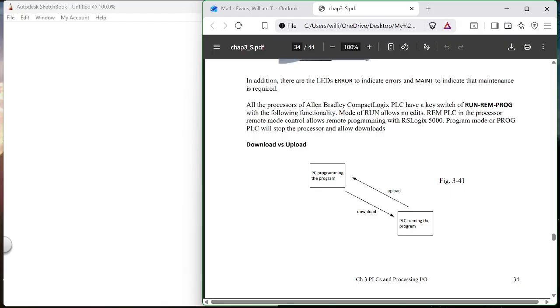And then there's a little green square in the Allen Bradley upper left. It's turquoise or green, and also both of them have what I call goalposts. Allen Bradley has them on the left and the right. Siemens only has them on the left. But when they turn green, you are running. When they're not green, you might not be running. With Siemens, you might not be running. With Allen Bradley, you're definitely not running.